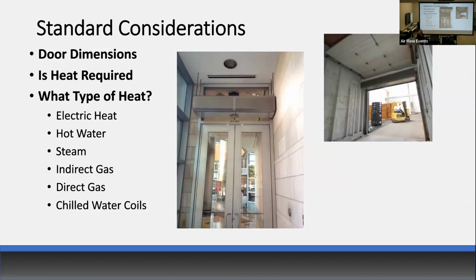Is heat required? If so, what kind of heat? Electric, hot water, steam, indirect, as well as direct gas. One thing I do encourage, if you are specifying a hot water or steam air curtain, check over the submittal of what you're getting. I know a lot of manufacturers will just stock coils. Reason being, it's cheaper. If you buy 200 at a time, you're going to get a much bigger discount. I know personally we made the decision not to do that. Prices might be a little bit higher, but sometimes you might need a 2-row coil to get a performance that matches what the building has. So please always carefully check what you're getting in terms of heat performance.